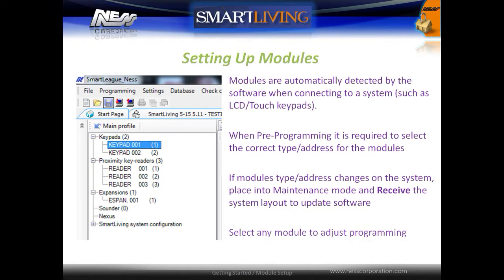Installed hardware modules, such as keypads and expanders, are automatically detected by the software when uploading from a system. When pre-programming is required, it is important to select the correct type and address for the modules. If any module's type or address changes on the system, place the system in maintenance mode and then receive the system layout to update the software. Once modules are added to your solution, you can then select them to adjust programming.